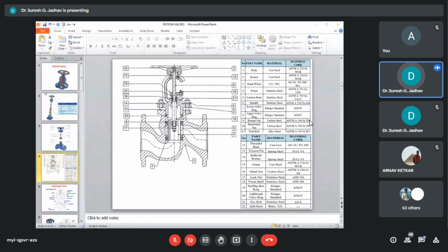The first one is the inside screw rising stem, and another is the outside screw and yoke (OS&Y) type with rising stems. That kind of stems are available in piston valves. The hand wheel is of the rising design, OS and Y type. A stuffing box with bolted gland is provided. This design is mainly used for thermic fluid or high temperature services.